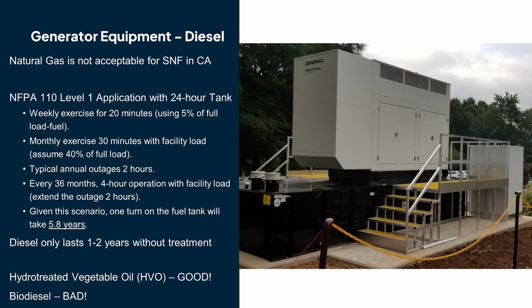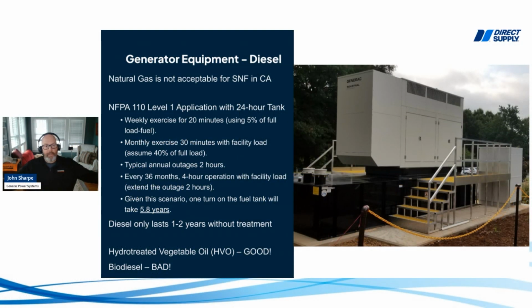This quick chart here - I won't read through it - but this was a 24-hour tank following standard recognized procedures for maintenance per NFPA 110, which you are required to follow. So the concept of just putting 96 hours of fuel on site, it's tough to do, frankly. Maybe get a 48-hour tank, and now we're talking about a memorandum of understanding for how you're going to get it supported.